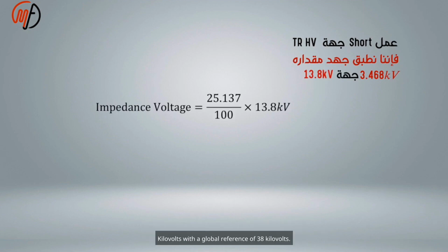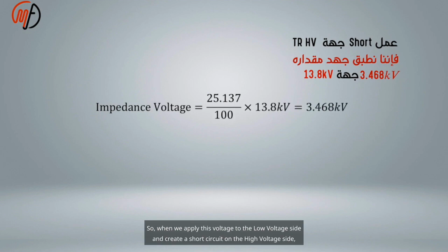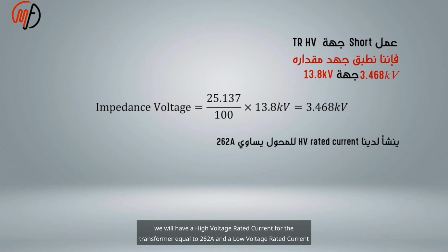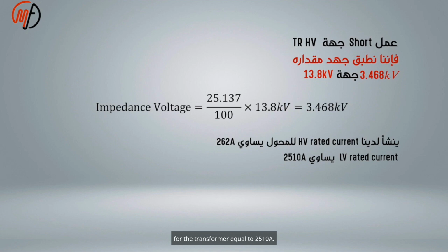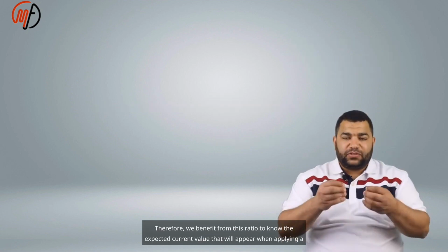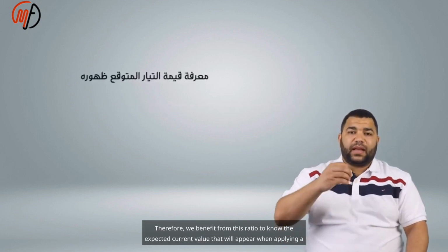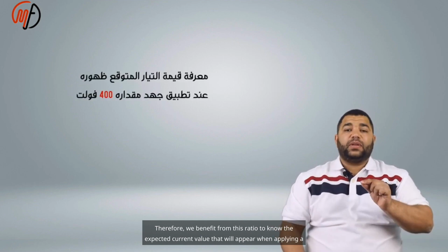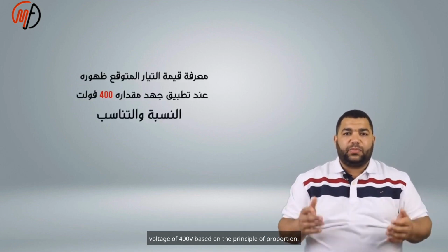Kilovolts with a global reference of 13.8 kilovolts. So when we apply this voltage to the low voltage side and create a short circuit on the high voltage side, we will have a high voltage rated current for the transformer equal to 262A and a low voltage rated current for the transformer equal to 2510A. Therefore, we benefit from this ratio to know the expected current value that will appear when applying a voltage of 400V based on the principle of proportion.